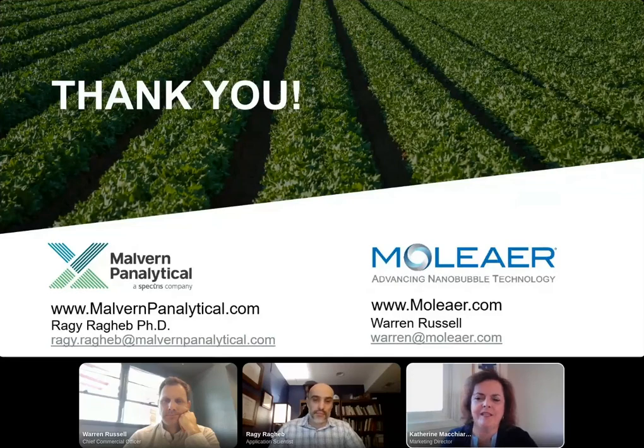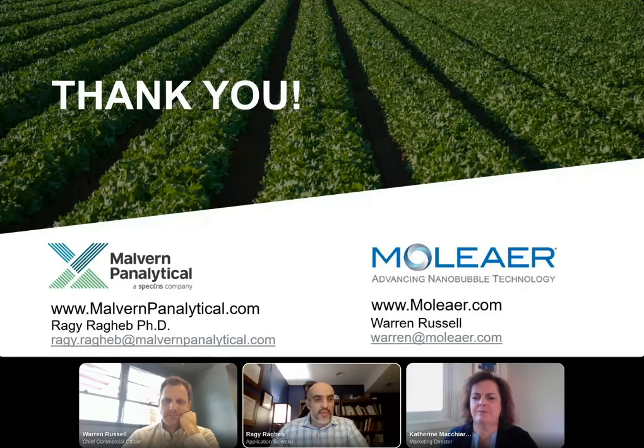What is the maximum salinity for measuring zeta potential in the Nanosight microscope? Right now, our current family of systems is reported to handle 250 millisiemens per centimeter, which is the highest salinity you can handle while making a reliable zeta potential measurement. You can read more on the specs of our equipment at our website, if you go to the Zetasizer product range.